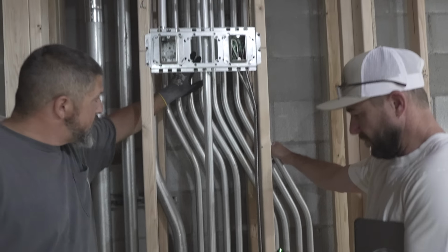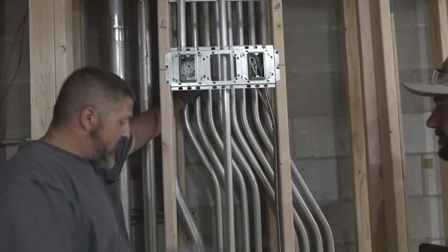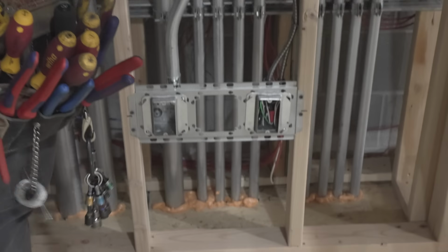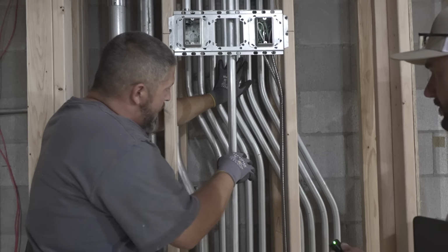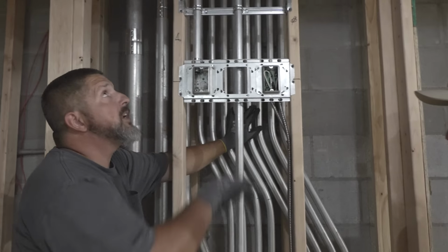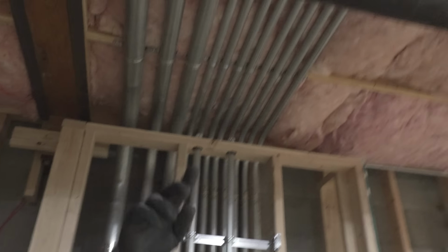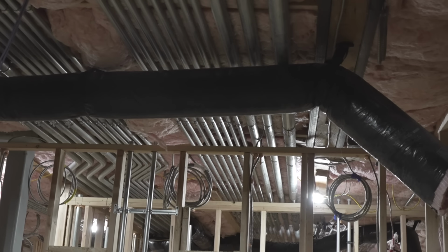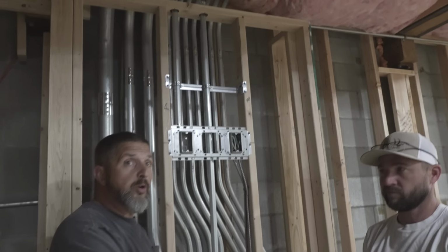I'm talking about this piping. So these 1-inch conduits here go down to the MDP, which is the main distribution panel. And they are for any high voltage power that we need on the way up through here, which is going to be for our rooftop units that come out of there for the breakers. And the 2-inch and the 2.5-inch are power that go all the way over to the other electrical room next to the stage for some panels over there for the stage panels.